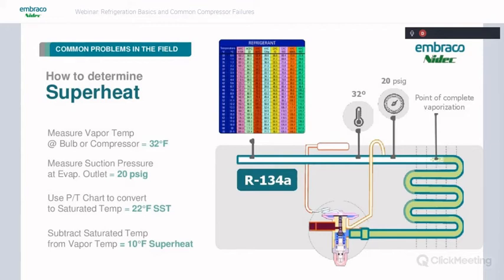We measure the suction pressure. In this system, we're showing 20 psig on the gauge, and then we're going to use a PT chart to convert that to the saturated temp, which is 22 degrees. And then we're going to measure the suction line, and then we're going to subtract these two temperatures, and that's going to give us the superheat. On this system, we're going to have 10 degrees of superheat. Typically, as an average, I like to say on a low temp system, you're looking for about 6 to 8 degrees of superheat, medium temp 8 to 10, and for air conditioning 10 to 12.